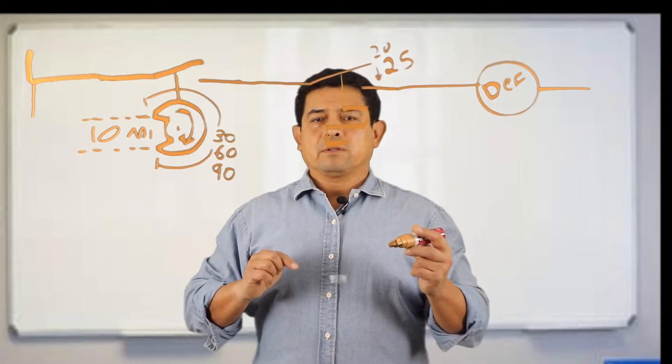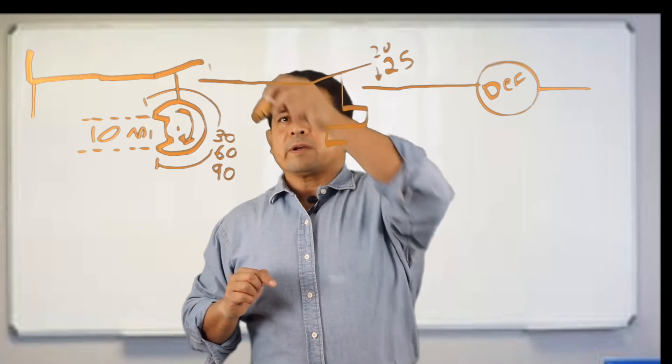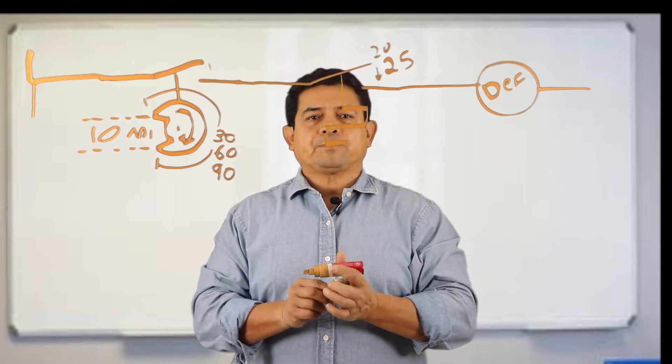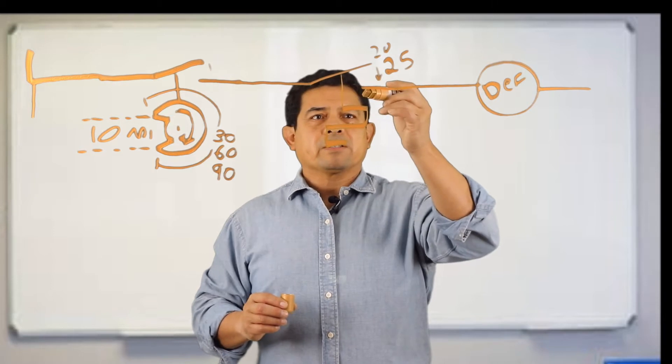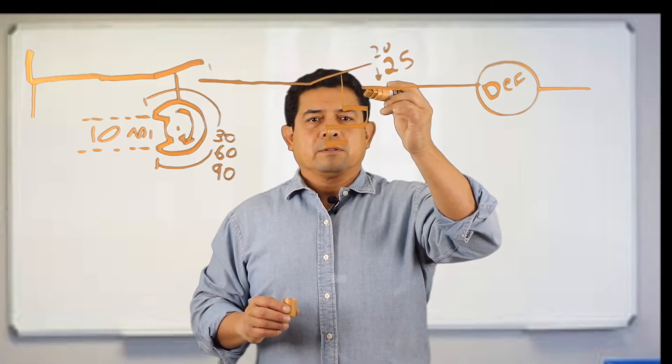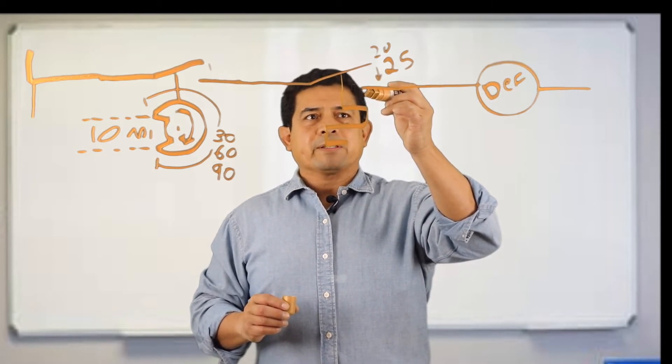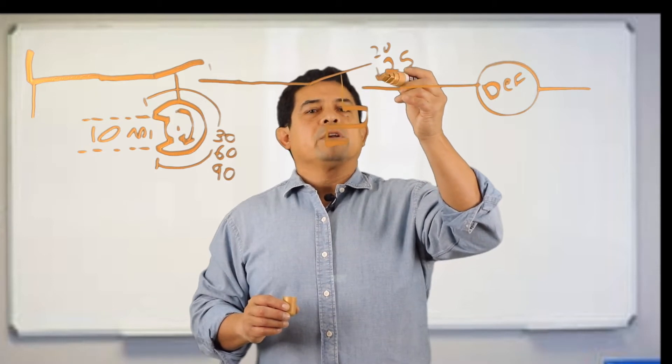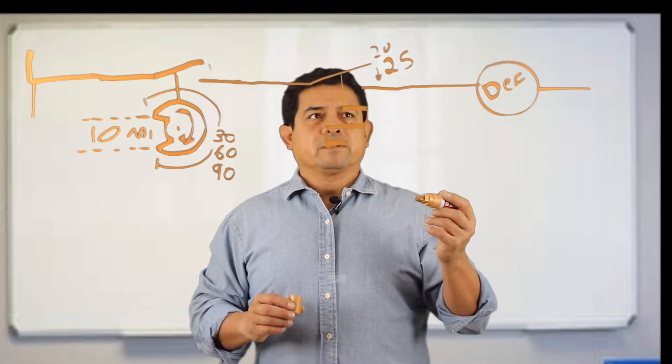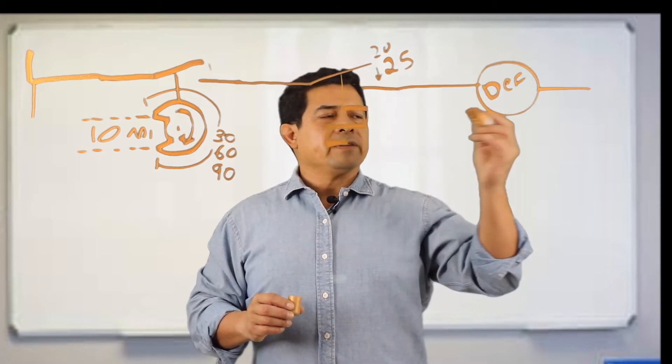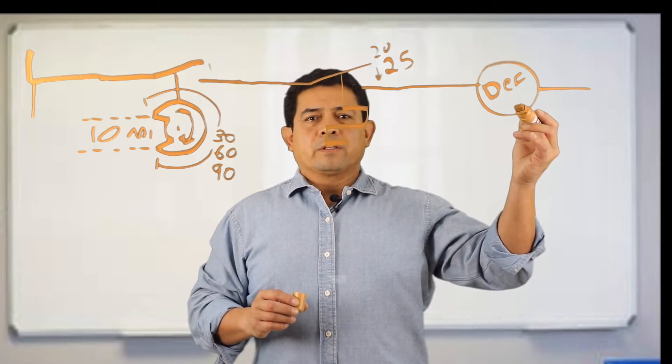Once these close, power is going to go through and stop right there. Power is not going to go through until the temperature drops below 25. Once it drops below 25, it sends power and goes into defrost.